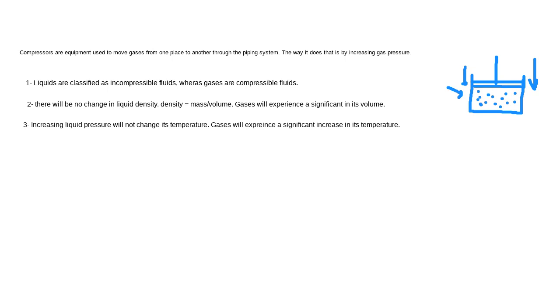اخوان، هذه الطاقة الحرارية راح تتسبب في ارتفاع ملحوظ، وارتفاع بعض الأحيان يكون كبير في درجة حرارة الغاز المضغوط. So that is actually the biggest difference between liquids and gases, is that the change in temperature is almost negligible in liquids، يعني تغير درجة الحرارة غير ملحوظ ولا يؤخذ به، بينما الغاز يا اخوان the suction temperature and the discharge temperature will vary widely. راح يكون في فرق كبير ما بين السكشن temperature والdischarge temperature.